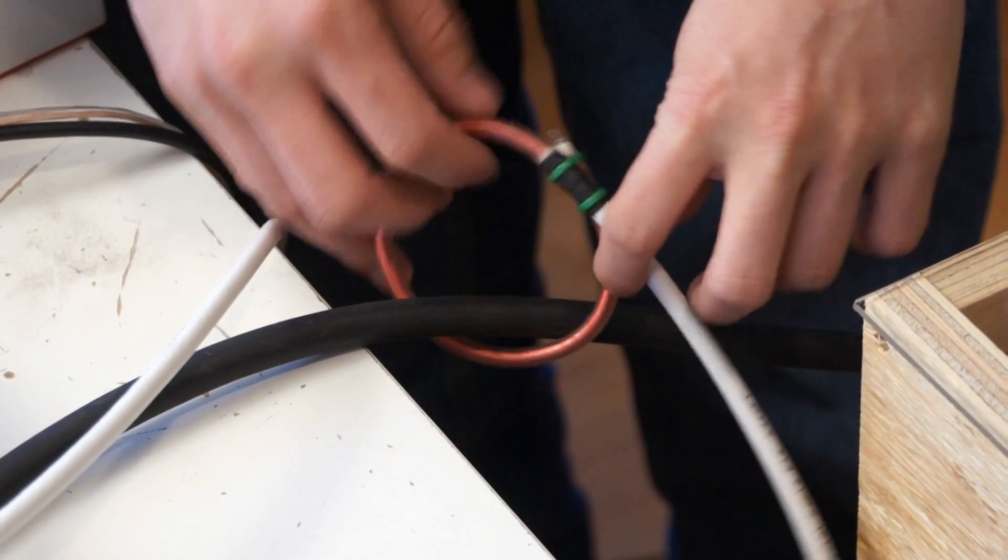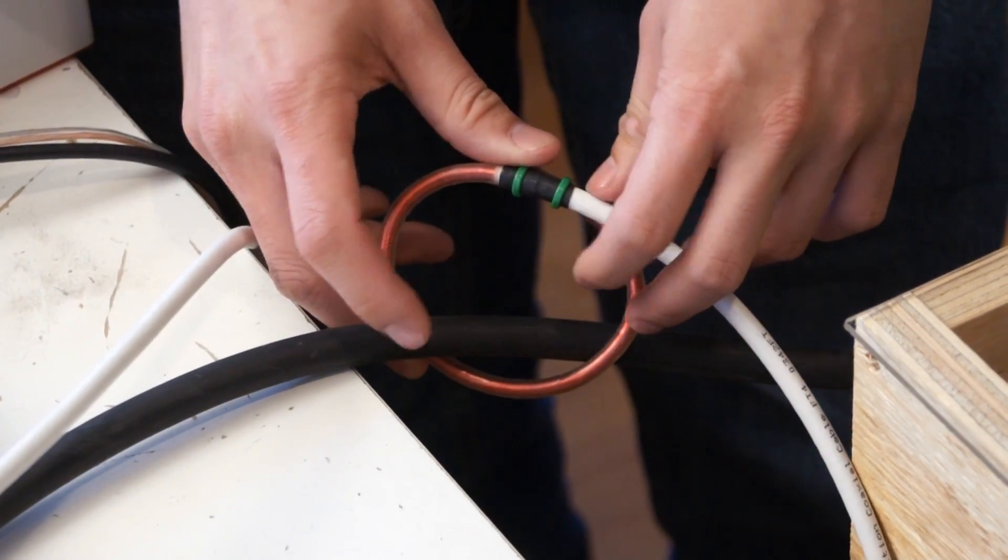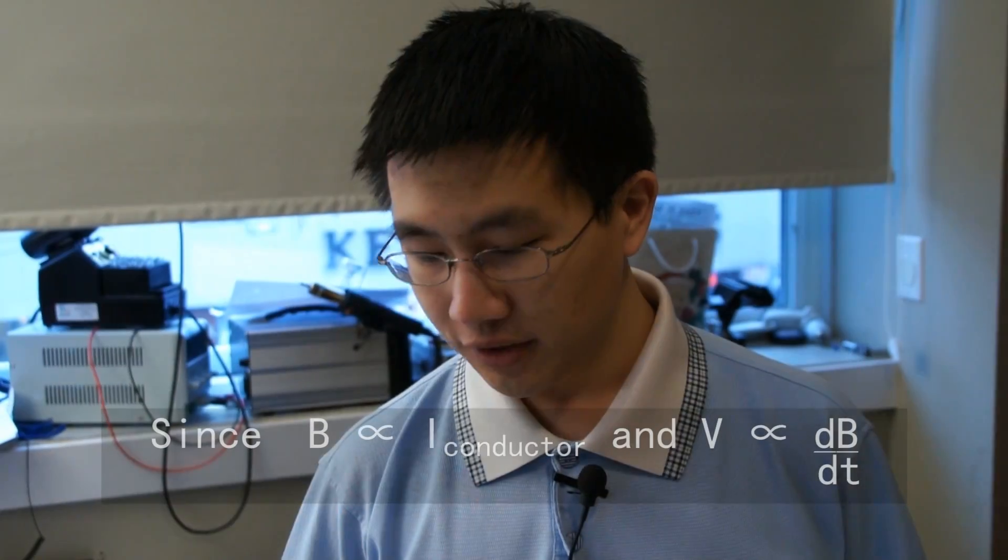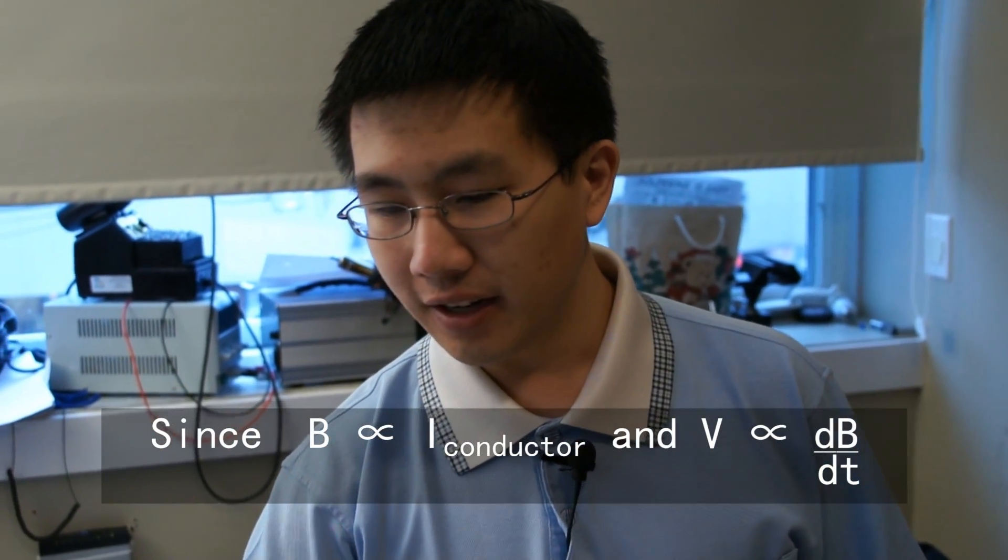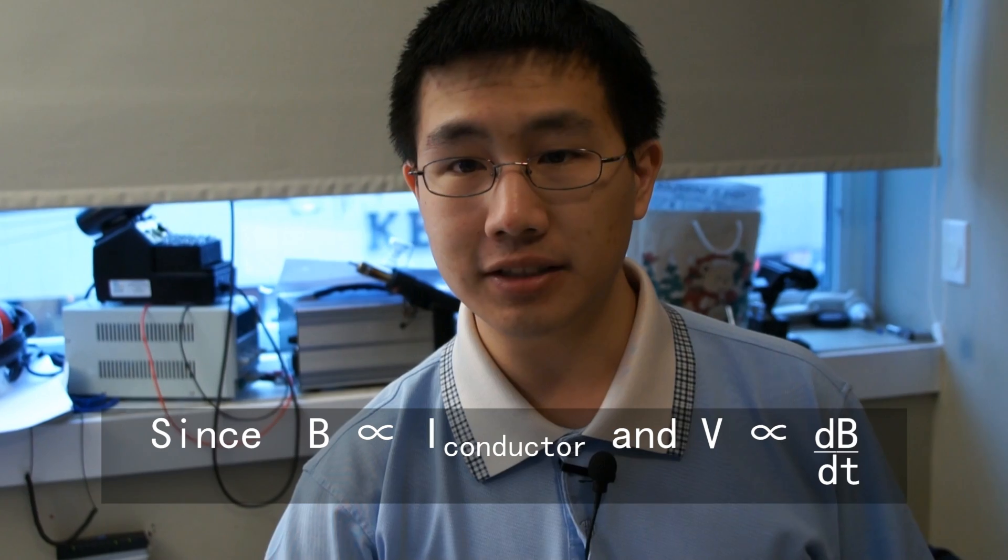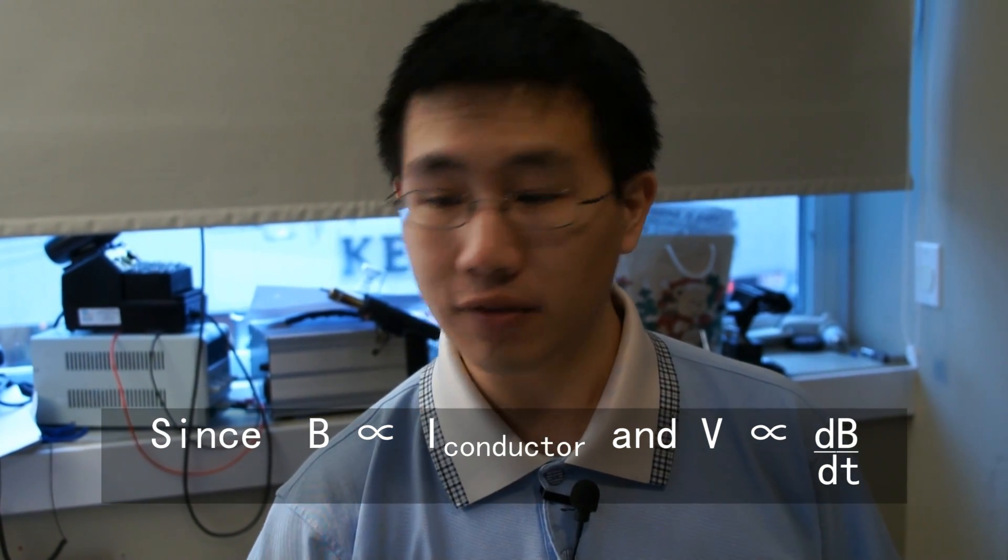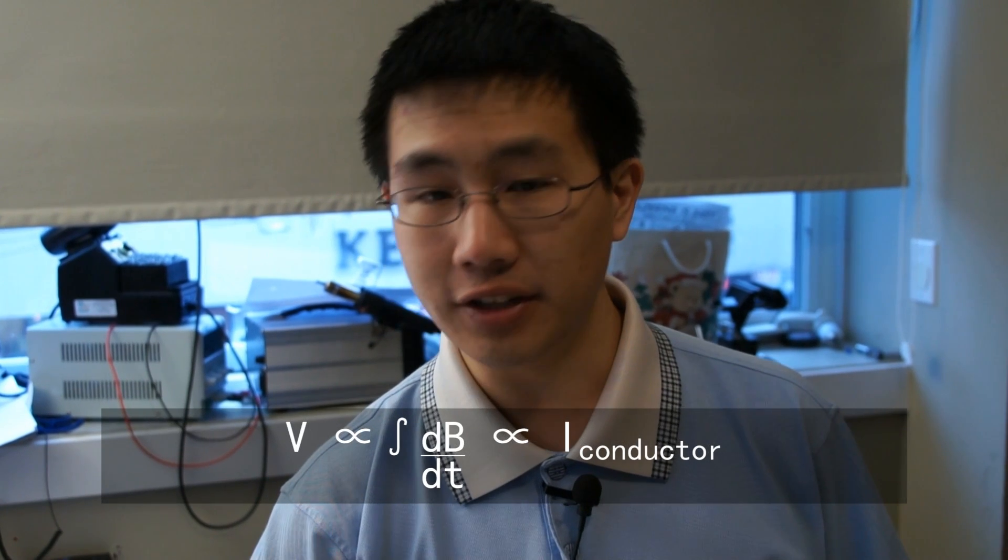Now this current sensor is actually something called a Rogowski coil. It's a flexible current sensor that you can wrap around conductors which are already installed. The Rogowski coil produces a voltage proportional to dB/dt, and in order to turn that into a signal that's proportional to the current flowing through the conductor, you need an integrator.